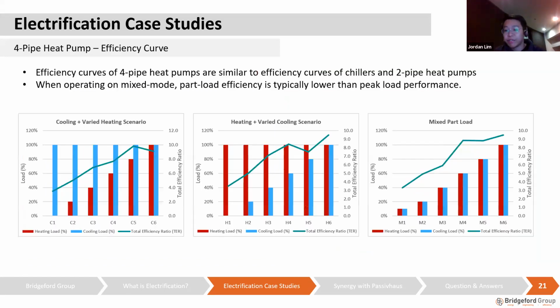Here are the efficiency curves for a 4-pipe system. If running on cooling or heating only, the efficiency curve is similar to a 2-pipe heat pump, so I probably don't have to share too much on that anymore. But when operating on mixed mode, it's actually better, right, when running on peak load. This is an example data set that I received from a close heat pump supplier of ours. So we've been working with this assumption for a lot of electrification projects.